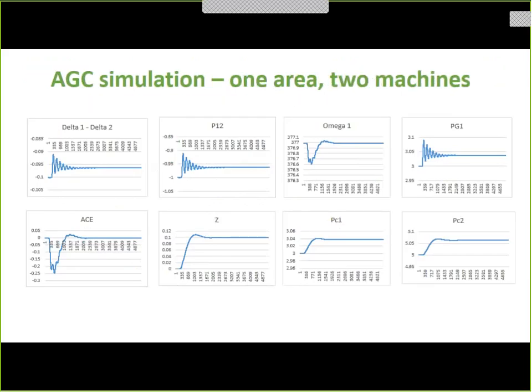Here's the answer. I increased the load in area at bus generator number two by 0.1 megawatts. It was 5, I think, and I increased it to 5.1, the load. That change in load created an error in the ACE, which was then integrated to get the Z variable. The Z variable is the integral of ACE, minus, integral of minus ACE. And you can see how the ACE dropped down, which meant you need more, right? If ACE goes negative with the NERC definition and it's minus, it means you've got to add more. So the answer was to increase the power set points for both generator one and generator number two.